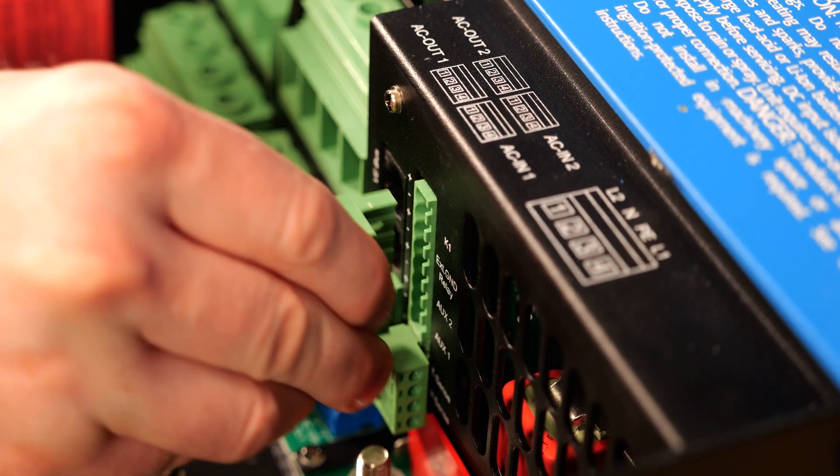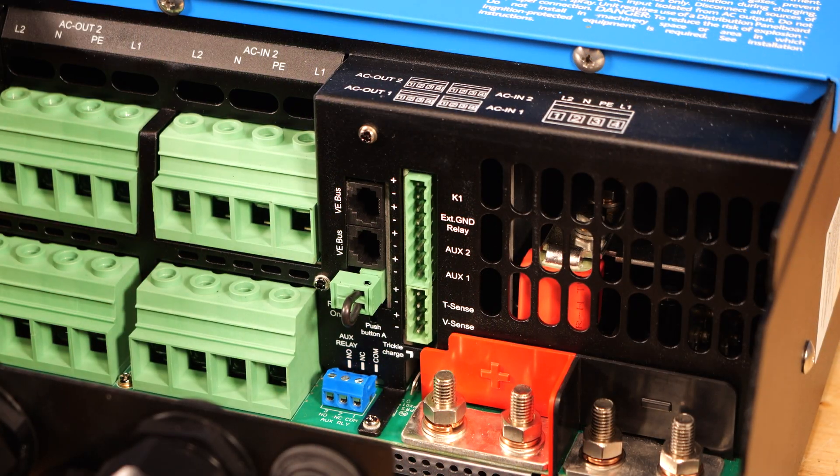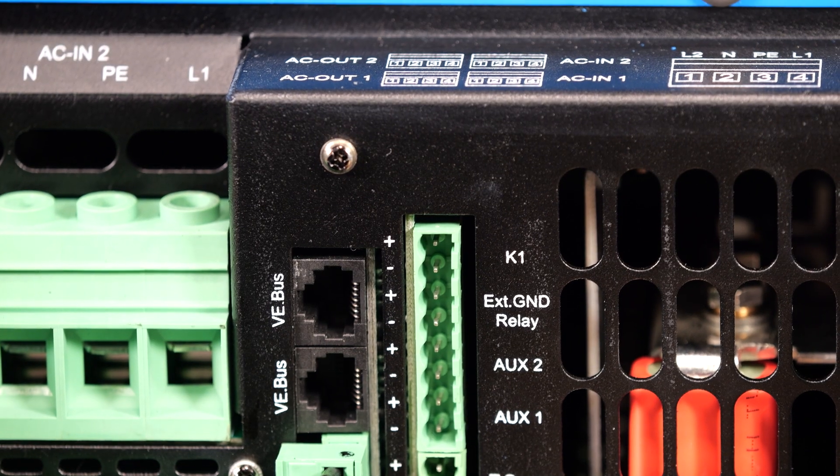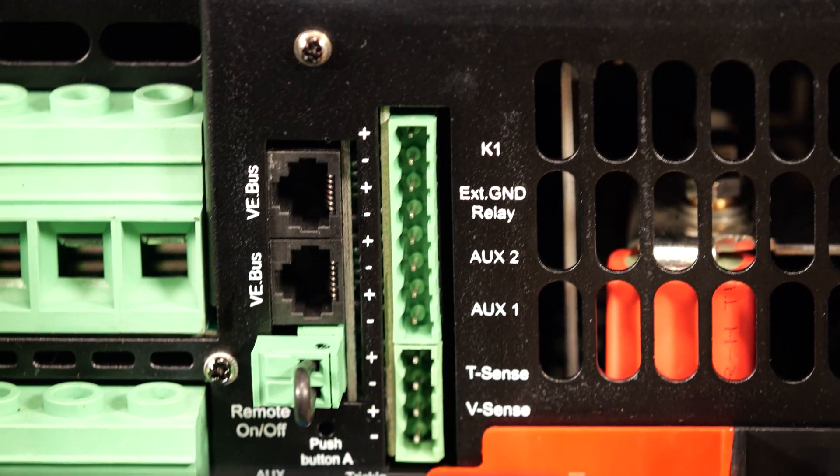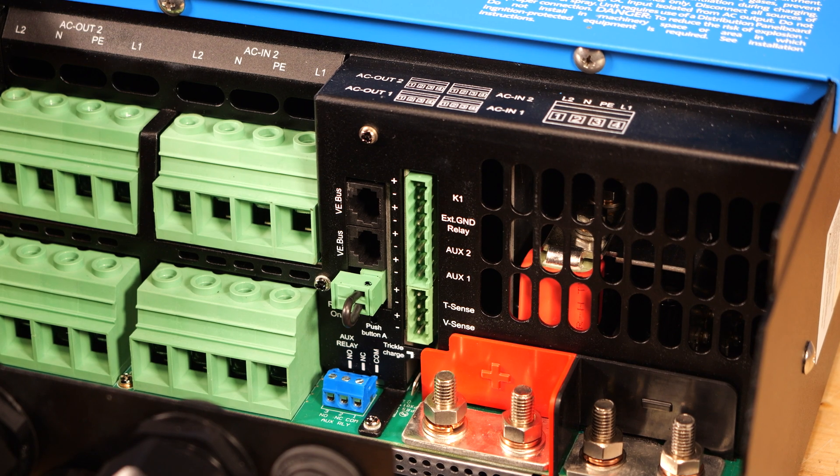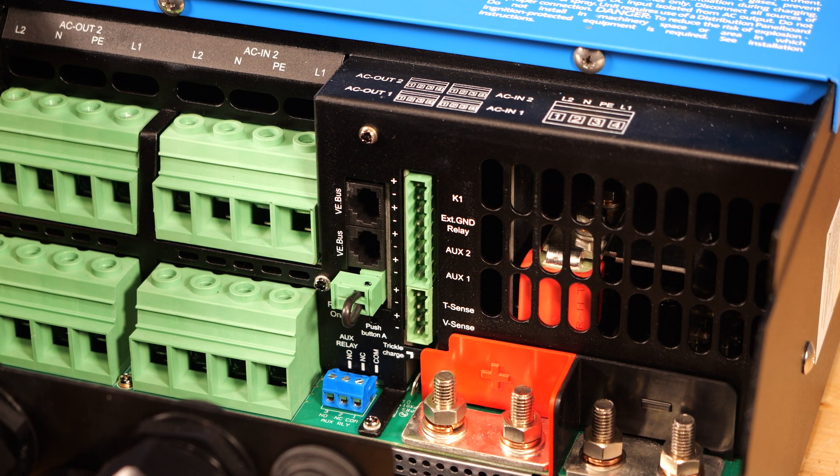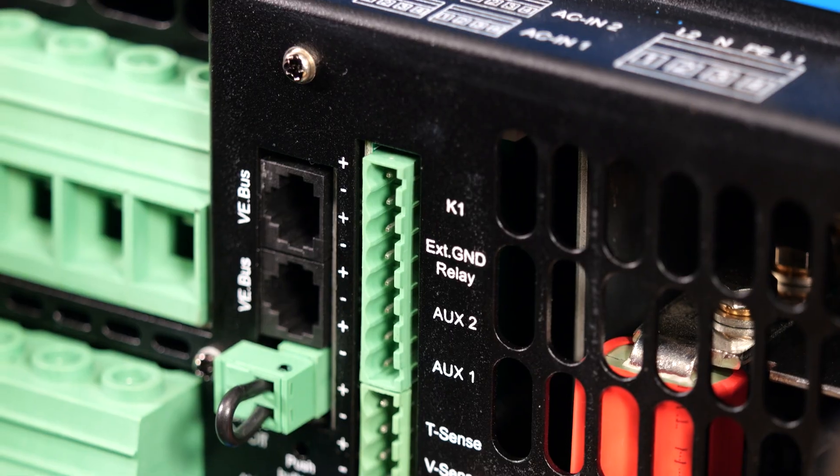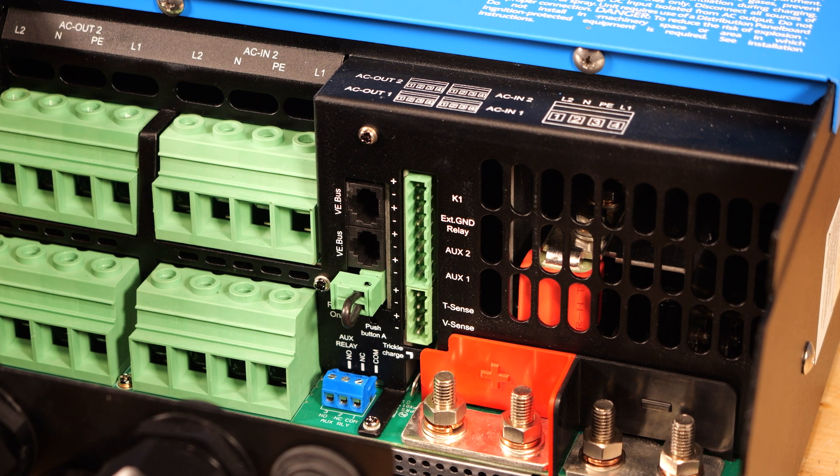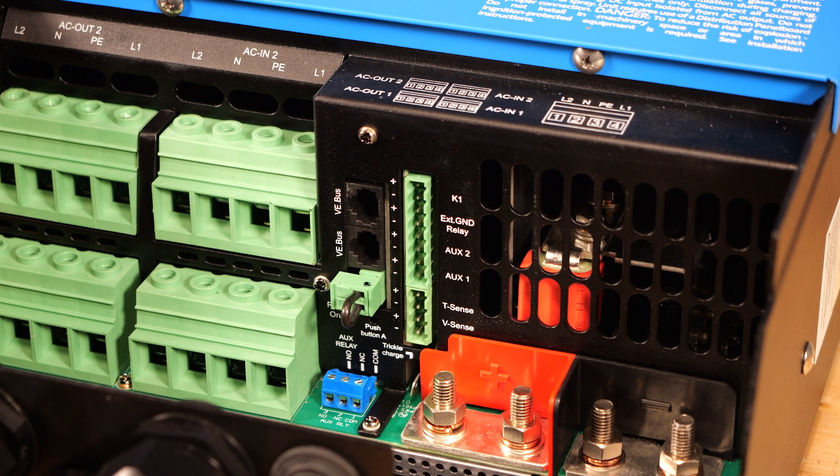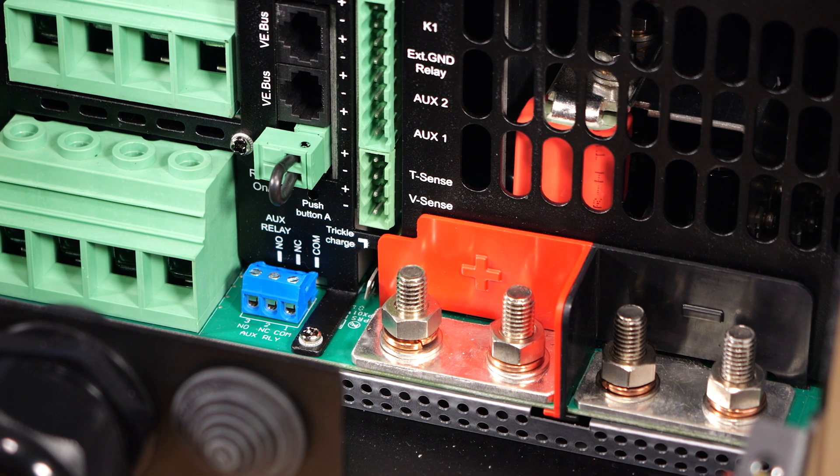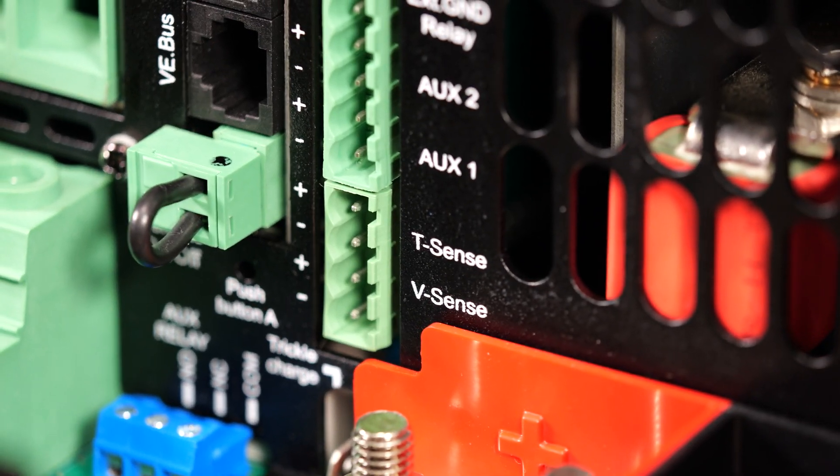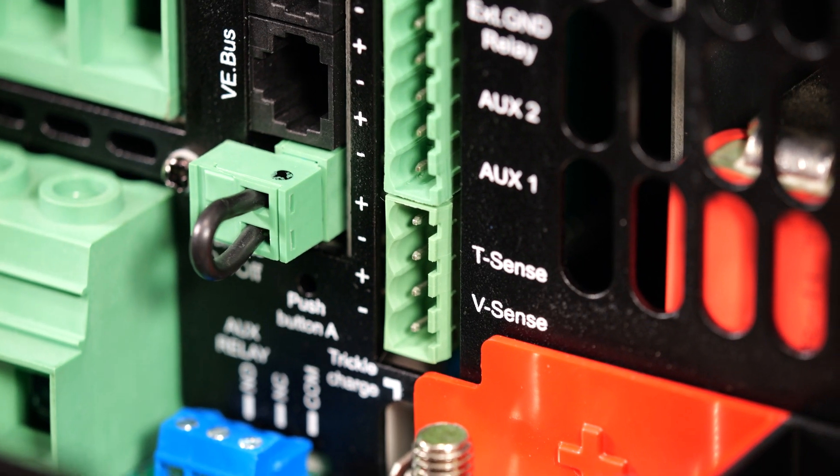Moving on to the green terminal blocks, we have four connections. K1 is a 12 volt output signal with up to 100 milliamps available. K1 can be programmed just like the auxiliary relay. The difference here is that it provides power, while the auxiliary relay can only switch power from other sources. Next, we have the external ground relay output and two auxiliary inputs. These inputs can be used with lithium battery BMSs for allowed to charge and allowed to discharge signals. Below that, we have the inputs for the included temperature sensors that can offer temperature compensation for lead acid batteries or low temperature charging cutoff for lithium.